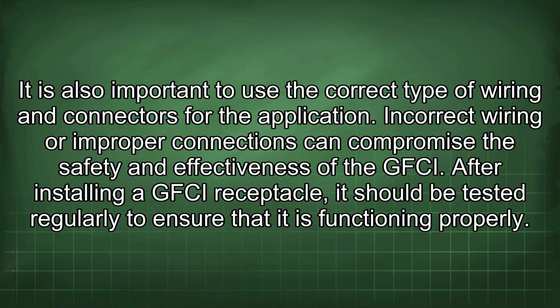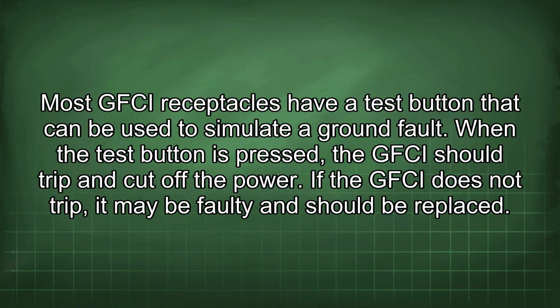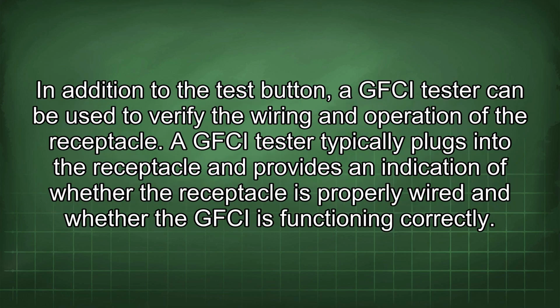After installing a GFCI receptacle, it should be tested regularly to ensure that it is functioning properly. Most GFCI receptacles have a test button that can be used to simulate a ground fault. When the test button is pressed, the GFCI should trip and cut off the power. If the GFCI does not trip, it may be faulty and should be replaced. In addition to the test button, a GFCI tester can be used to verify the wiring and operation of the receptacle. A GFCI tester typically plugs into the receptacle and provides an indication of whether the receptacle is properly wired and whether the GFCI is functioning correctly.